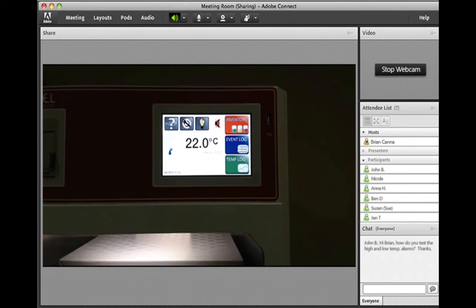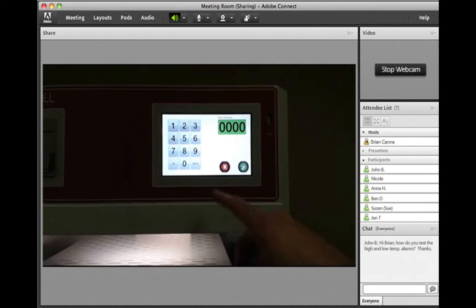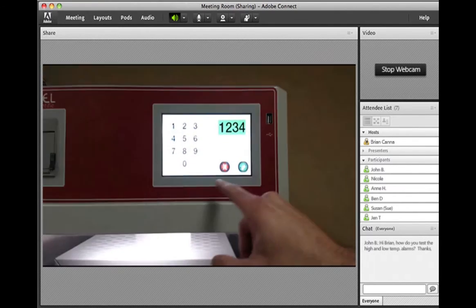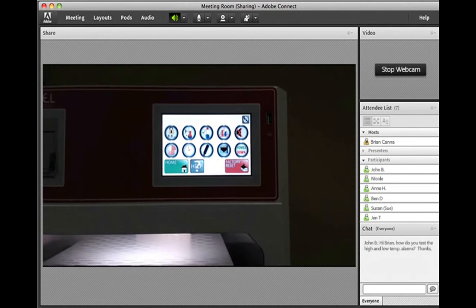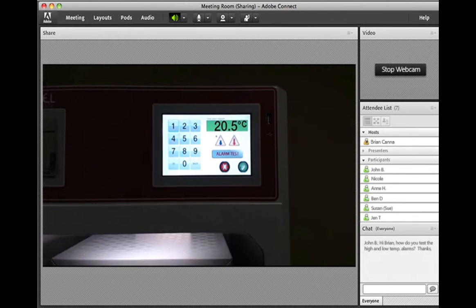So I think that looks pretty good on the screen. We'll go into our settings menu, enter our passcode, alarm icon. So our alarm test is a little bit different than some procedures out there. The unit actually takes control of the Peltier and it will heat the system up, and if it goes above the high point, it will alarm. If it goes below the low point, it will alarm. It's much better than removing anything or putting stuff in ice water. This is actually all programmed into the unit to make testing those alarms very easy.